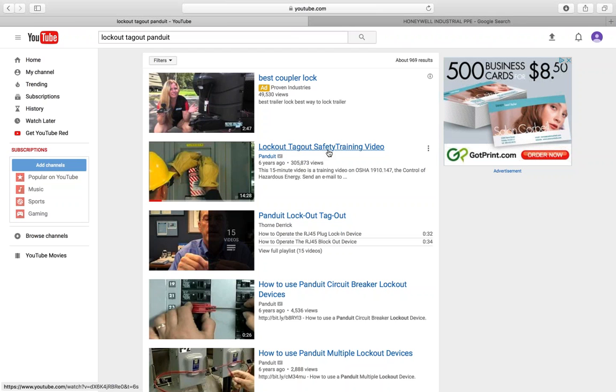However, in OSHA maritime, there's a program called Lockout Tagout Plus. With Lockout Tagout Plus, this all started back in 2010 or 2011, if a piece of equipment on a maritime vessel is capable of being locked out, it must be locked out. And not only that, they went a step further and said if it's anything that was revised on a vessel after 2011, if it was an energy isolation device, like a gate valve, a blind, a breaker, it had to be capable of being locked out too.